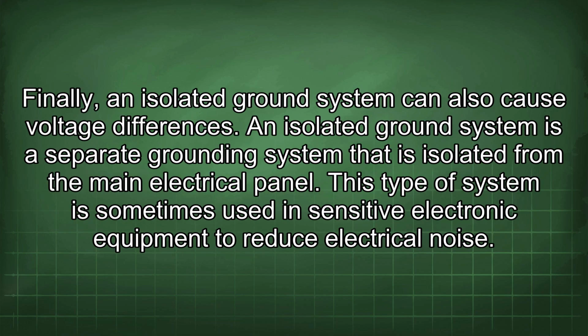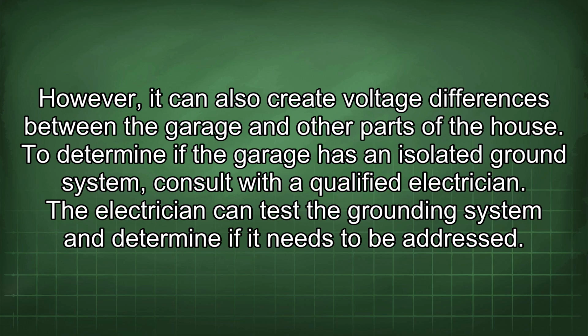Finally, an isolated ground system can also cause voltage differences. An isolated ground system is a separate grounding system that is isolated from the main electrical panel. This type of system is sometimes used in sensitive electronic equipment to reduce electrical noise. However, it can also create voltage differences between the garage and other parts of the house. To determine if the garage has an isolated ground system, consult with a qualified electrician. The electrician can test the grounding system and determine if it needs to be addressed.